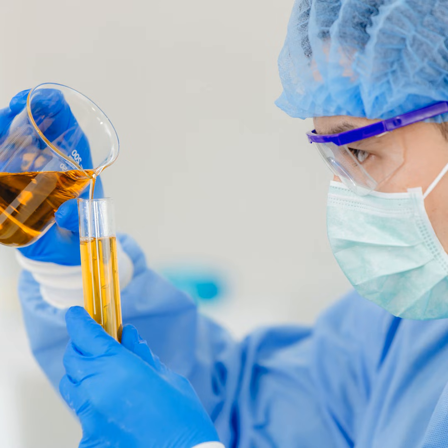Thirdly, particle counting is based on particle size rather than particle material, whether it's performed using microscopic analysis or automatic particle counters. And finally, perhaps the most important lesson of all, even the most sophisticated measurement system depends on one critical step: taking a representative oil sample. Without that, the numbers simply can't tell the real story.